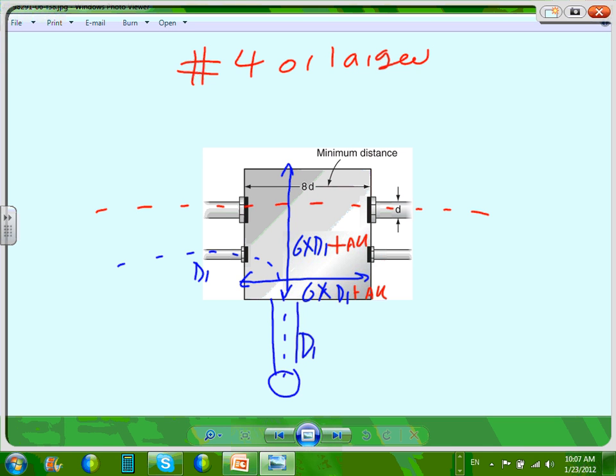Please, guys, I encourage you to look at the example that we did. We have a really nice example, and it's on YouTube now, with multiple conduits coming in all over and all the calculation for it. The only thing I want to emphasize: if you're going straight, it's 8 times the diameter of the largest conduit engaged in the straight. If you're going with an angle, it's 6 times the largest diameter engaged in the angle, plus all the conduits sharing the same wall. If you're looking at this wall, nothing is sharing. If you're looking at this distance, you're looking at this wall, then there's another one sharing.